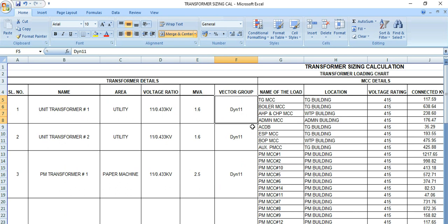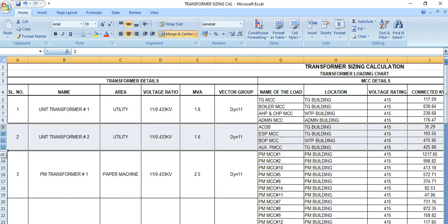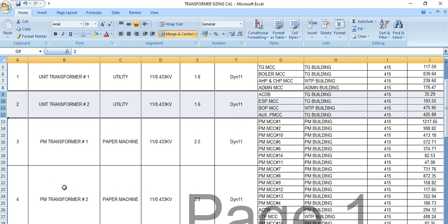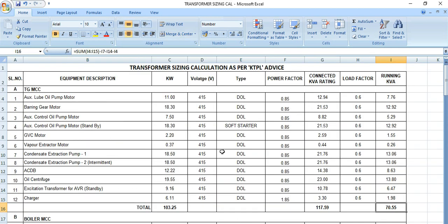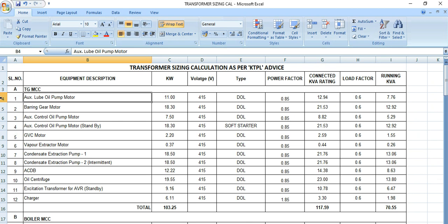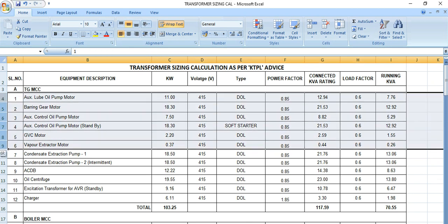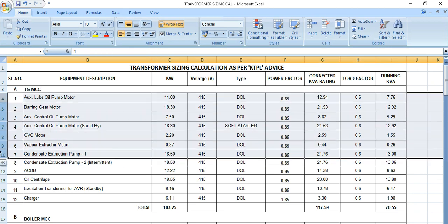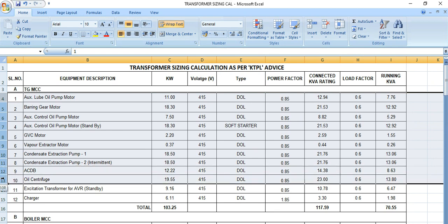In this way we have sized all other transformers as well. First of all, we need to see what are the individual loads. Let's say for this particular MCC, there are some motors, there may be some power feeders, any lighting transformer, welding receptacle.